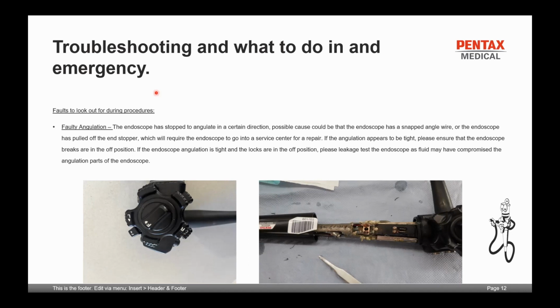If the angulation appears to be tight, the first thing you would check is the free lever locks. So that is a free lever lock. Most endoscopic companies have free lever locks on the endoscope. And sometimes while the endoscopist is performing this procedure, his gastroscopy or colonoscopy, he accidentally tightens the locks. The endoscopists generally know themselves where to look for that. But if you get called in, have a look and make sure that the locks are in the free position and are not activated on the endoscope.